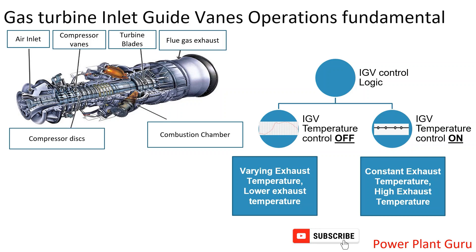If you increase the load, fuel is increased and temperature would go higher — but if you are already at the highest temperature limit, the IGV will increase its opening to maintain that temperature. Similarly, when reducing the load, you are reducing the fuel so temperature tends to fall, and the IGV will reduce its opening to maintain the original exhaust temperature.